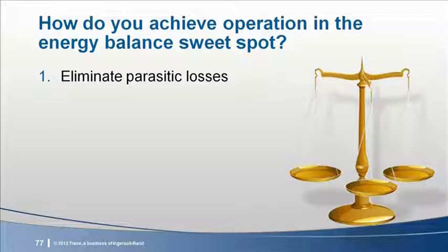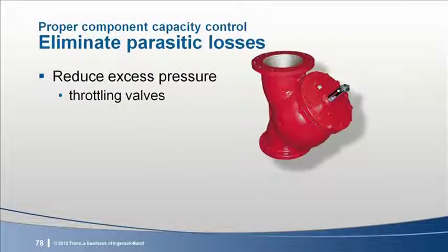There are 3 keys to achieving operation in the system's energy balance sweet spot. The first is to eliminate parasitic losses. A parasitic loss is a process where energy is consumed, but no useful work is performed. A perfect example of an avoidable parasitic loss is a throttling valve, such as a triple duty valve on a pump. When a VFD is used to control a pump, there is seldom a reason for the waste and cost of a triple duty valve. Even if active variable flow is not planned, the pump speed can be adjusted to commission the pump flow at a greater savings over the triple duty valve restricting flow.